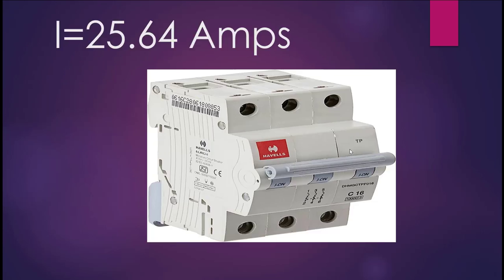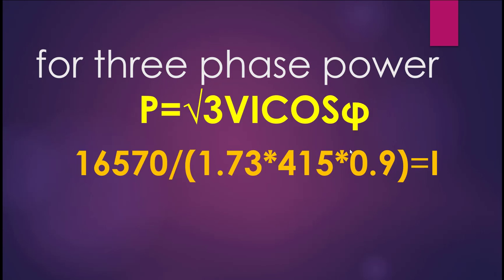That's about 16.5 kilowatts. Now just to remind you, for single-phase power we have P = V × I × cosφ. When three-phase power comes in, it becomes P = √3 × V × I × cosφ. Where the √3 comes from and its significance, we'll explain separately as it would take more time. So quickly: P = √3 × V × I × cosφ. For √3 we use 1.73.